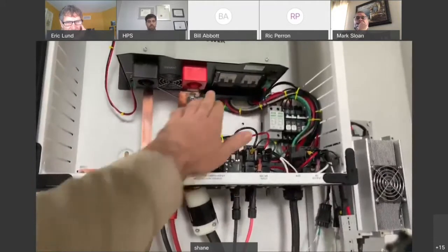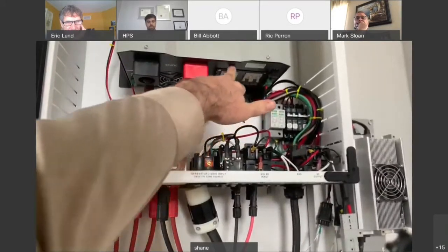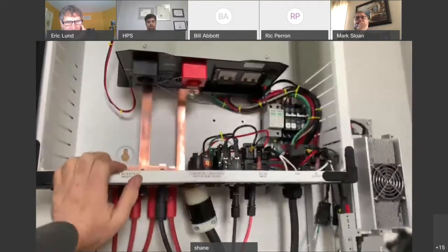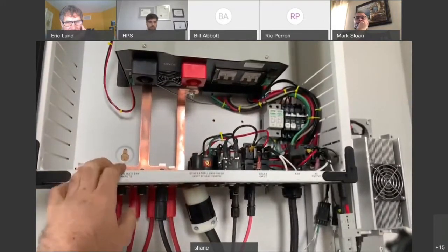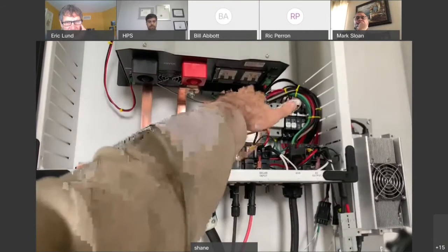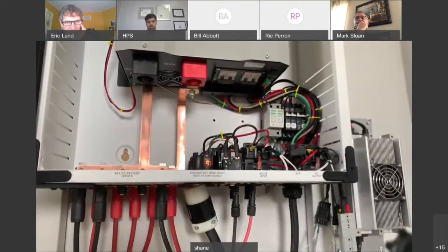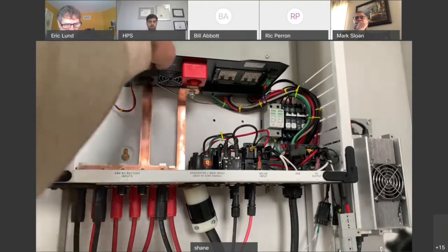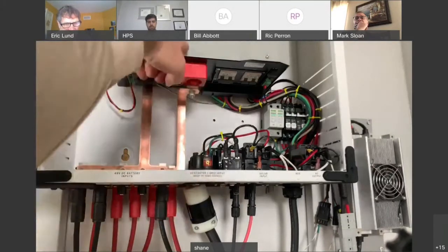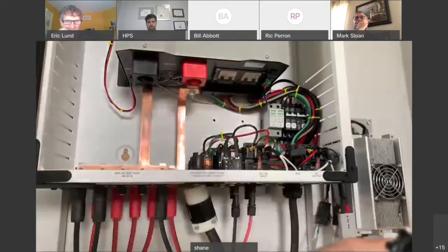So this guy is our input from the grid or from our generator. That's a 30 amp breaker, I believe, that's protecting the charging circuit and the transfer circuit. And here we have our output 2-pole, and that's going to be our 30 amp output towards your load. The way these work, just really quickly, is when there's AC present and you're in normal operation, it will bypass the load through an internal transfer switch. So your generator is coming in, going through there into the transfer switch, and then back out to your load. So when you are charging, you're pulling everything directly from the generator. There's no bidirectional DC current happening. You're only pushing into the batteries.